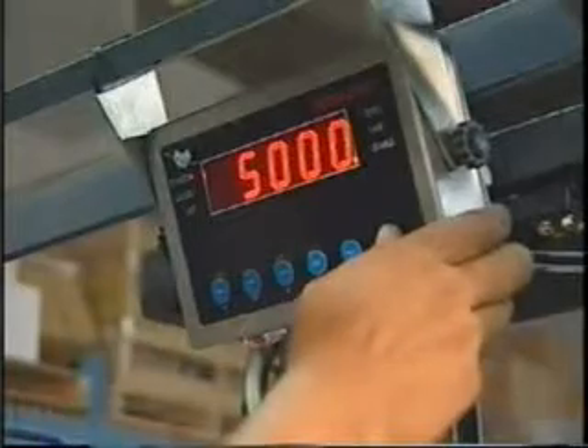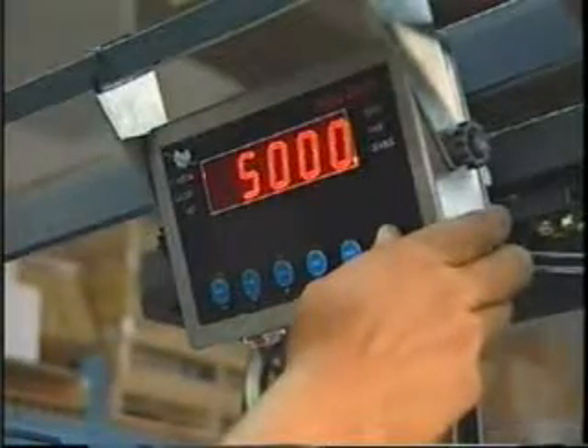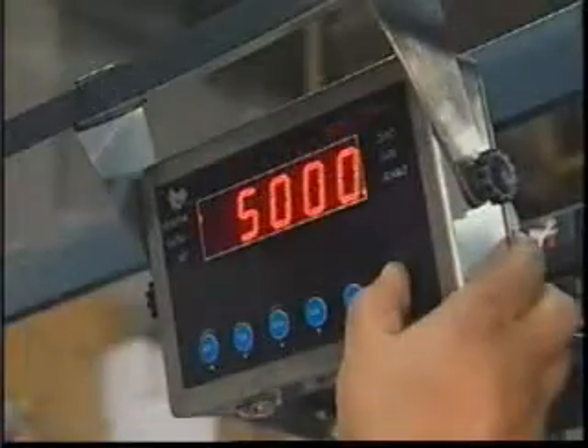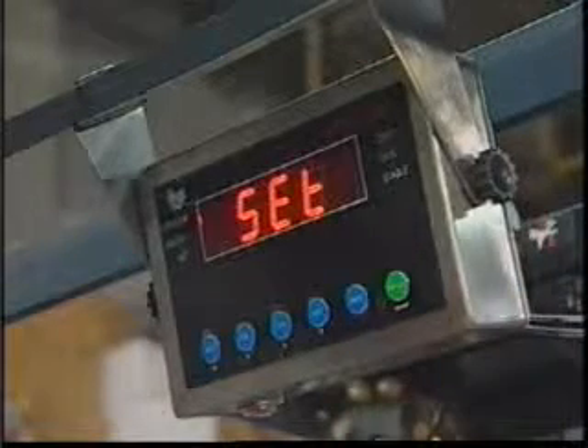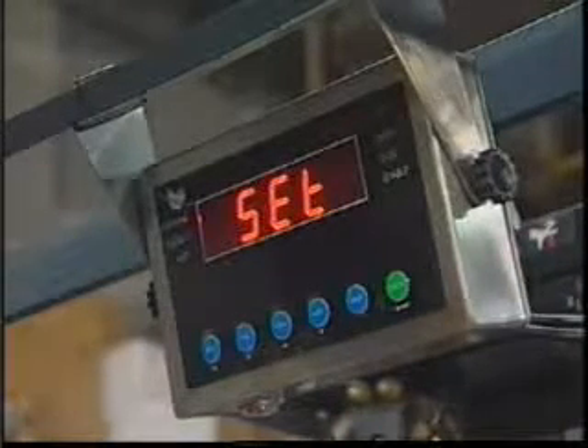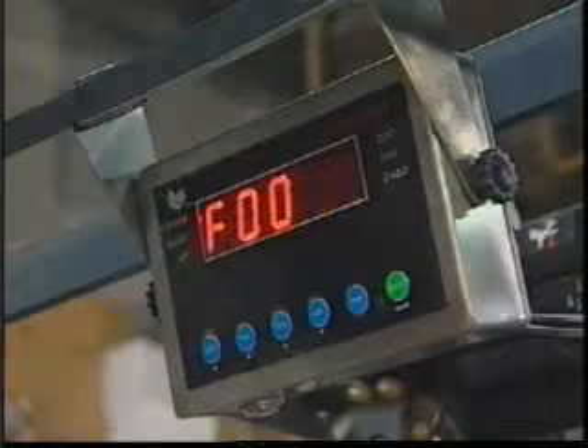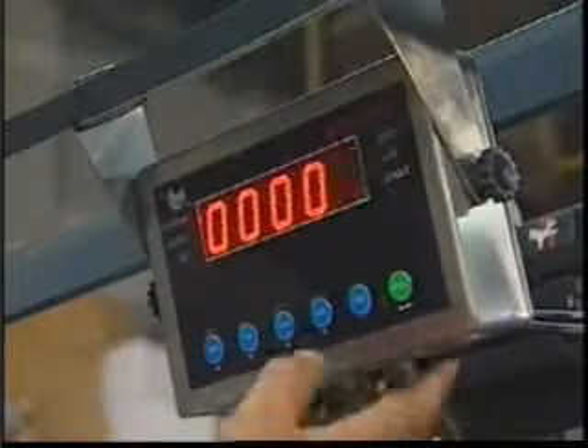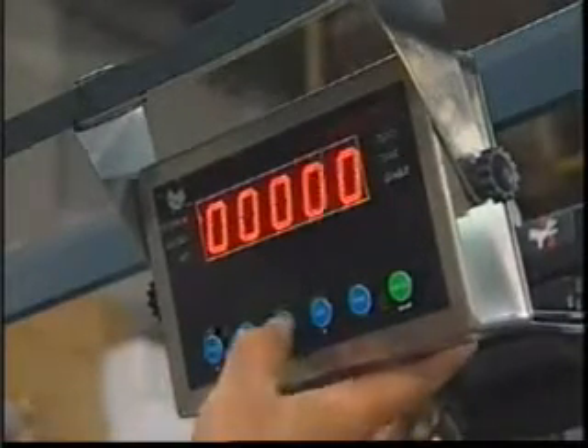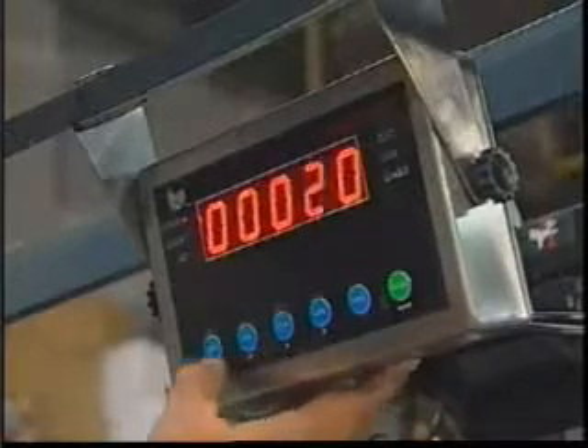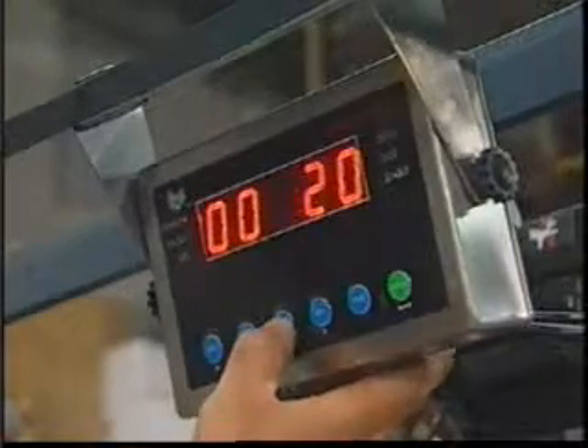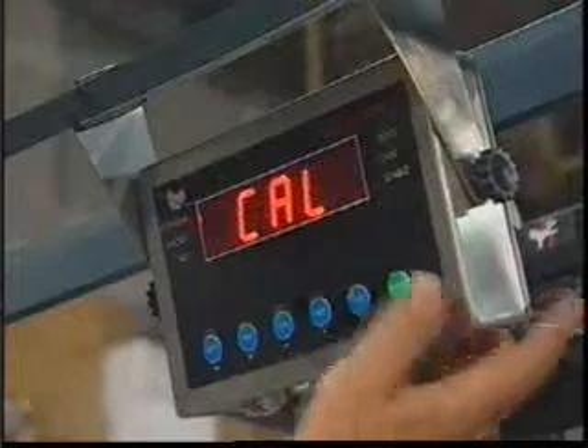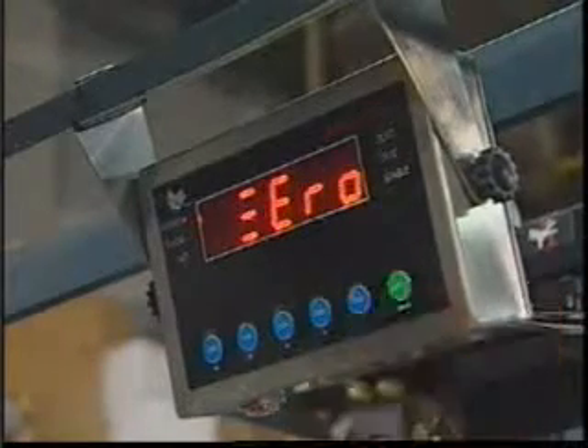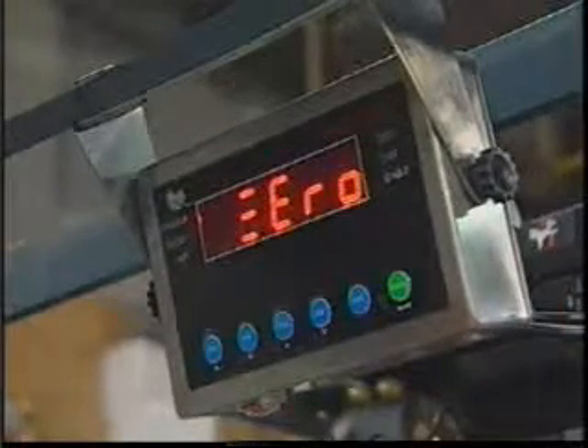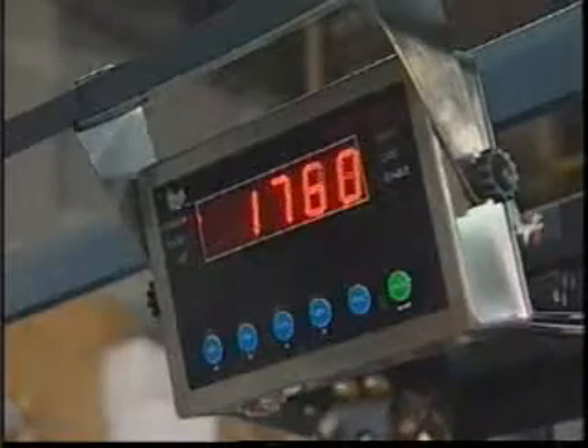Start the forklift and proceed to shut off the display unit using the switch. Then, while holding the weigh key, switch the display unit back on. After a few seconds, the display unit will reach set, and you can release the weigh key. The unit will then read F00. Press the weigh button, and then using the shift and increment buttons, enter the number 00020 and press enter. Press the weigh key again, and the unit will specifically request the zero weight of the forks.